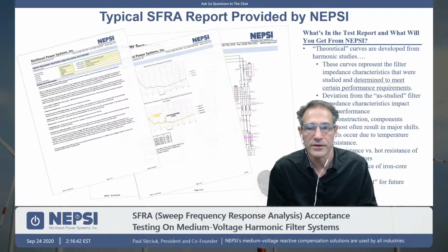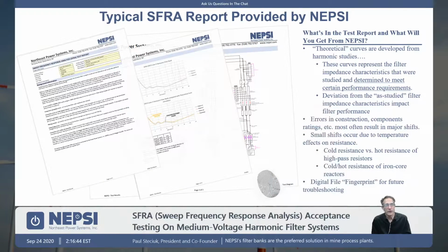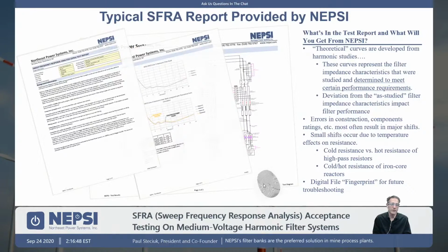So again, we talked about the test reports. One thing I want to talk about is this fingerprint here. This is something that's used by transformer suppliers. They do an SFRA on a transformer to get a wave shape. But we do the same thing. We keep a digital file of the SFRA scan. If in the future, for instance, there were a fault inside a harmonic filter, the first question somebody will ask is, is my harmonic filter safe to use? Is it healthy? Is there damage?